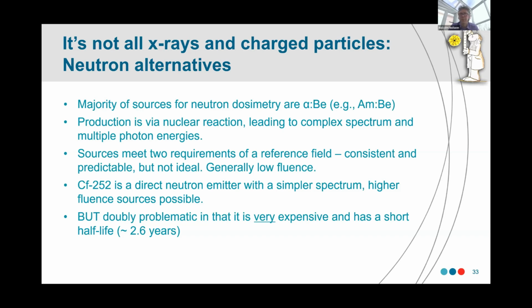Sources do meet two requirements of a reference field. They're consistent and predictable, but they're not monoenergetic, which would be nice. But they're well used, they're easily accessible, and they have become embedded again in the system for calibration. The other source that's commonly used is californium-252, which is a direct neutron emitter, has a simpler spectrum, and higher fluence sources are possible. And there's a big but here, always a but as you'll see in this presentation.